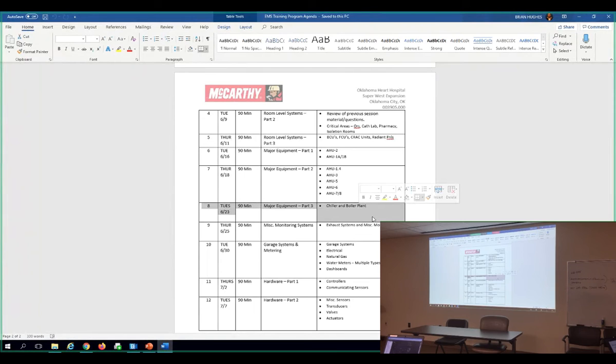No. Well, the boilers have their own boiler management system from the vendor, so that'll mostly be covered in United's boiler training. These guys really just pick up a few points and enable. We're just turning it on and sending a set point. And it's an outside air reset too. Right. Maybe we do a brief overview on that and jump straight into AHUs on Thursday.